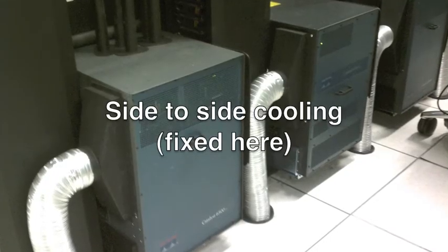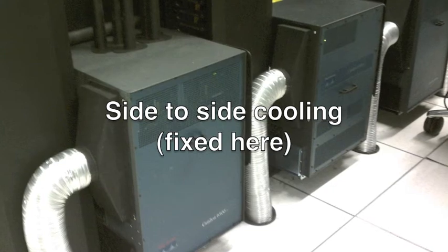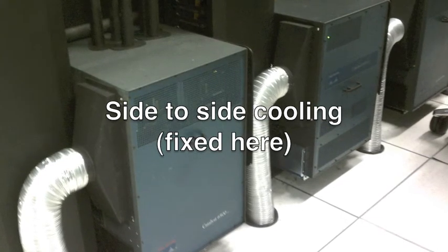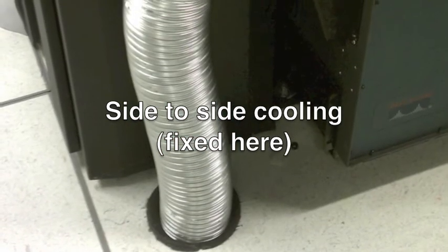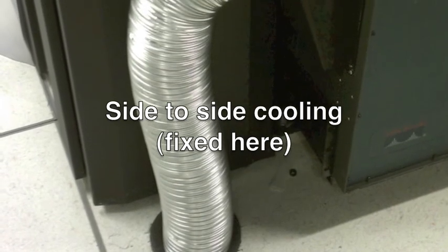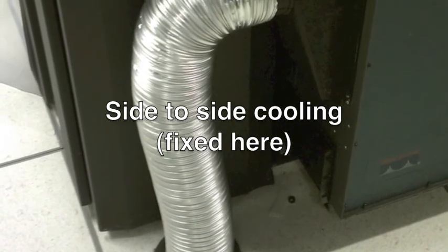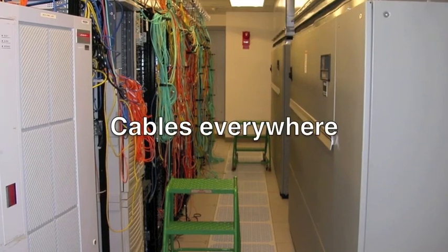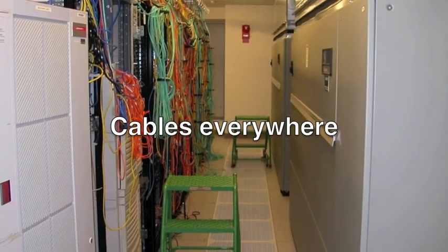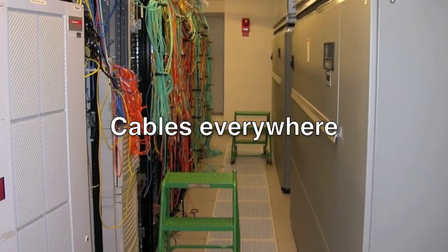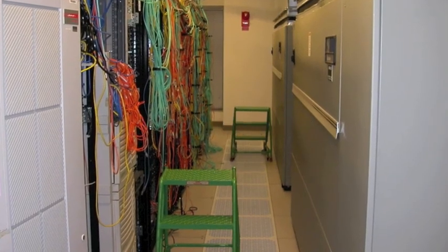The Cisco 6500 switches have side-to-side air cooling. In this case, it's actually already been fixed, but it's another thing to look for in terms of making sure that we have hot and cold separated in our design. Of course, cables need to be considered in all designs. We don't want to pinch them. We have to work around them and leave room for them.